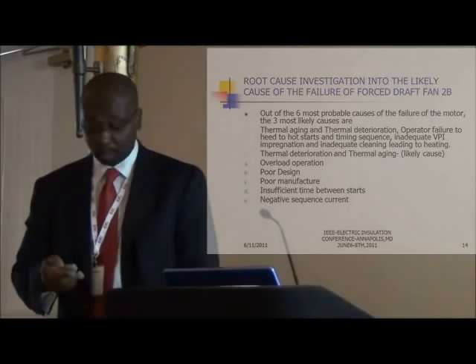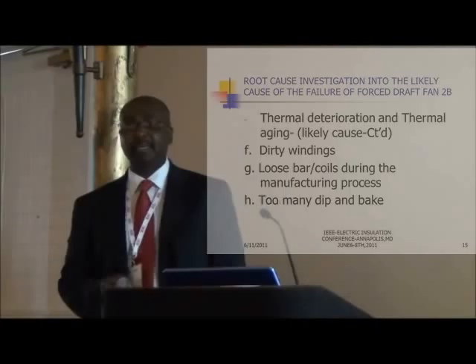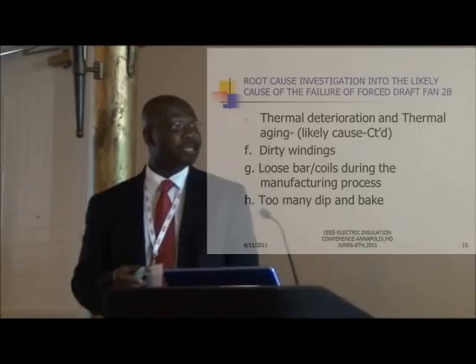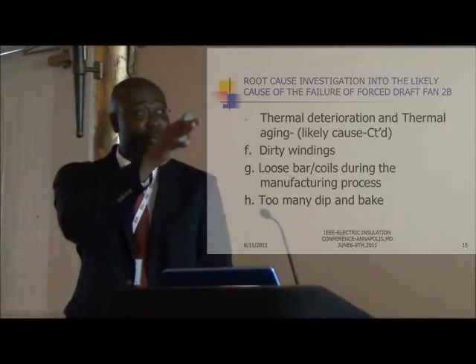Dirty windings can cause a significant increase in temperature, which is a result of not having a good PM program in place to clean the filters. Loose coil bars during the manufacturing process can also contribute to thermal aging. While loose coil bars were not confirmed as a cause here, too many restarts was found to be a contributing factor to this motor's failure.